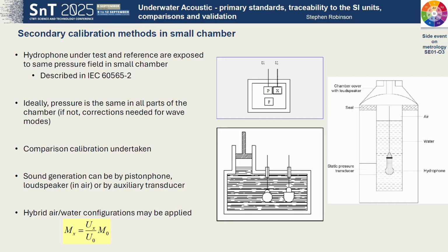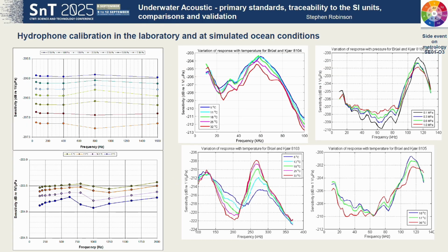The difficulty here, though, is that because you're doing secondary calibrations of devices that will be used in the field, you need to consider whether your calibration represents the performance of that device in the ocean conditions that you've got for deployment. And some hydrophones can show variations in sensitivity with depth and temperature. So here on the left, I've got some examples measured from our coupler reciprocity, showing the variation with depth of a hydrophone sensitivity across lowish frequency range from 20 hertz to a kilohertz or so. On the right, you've got some measurements against temperature and depth, but they are at higher frequencies, but they illustrate the same principle.